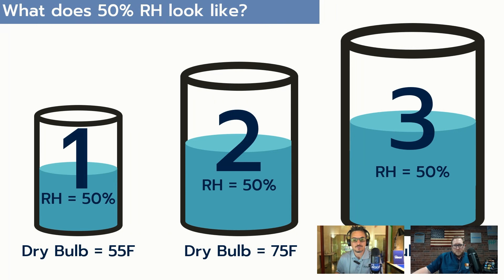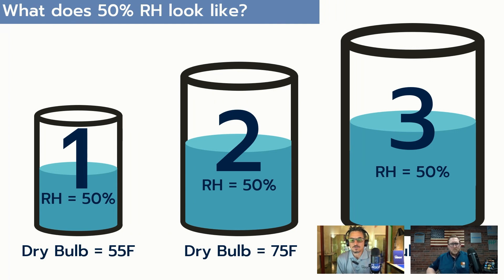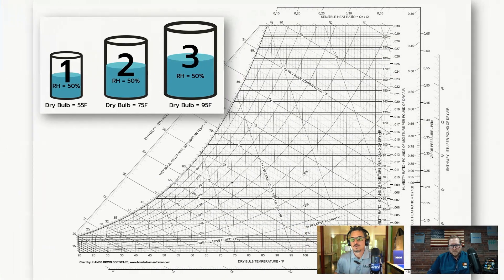We'll throw some numbers on here because we're going to reference them in a moment. What do you notice about the water volume in these three containers? It's a lot larger in container three than one. That's the flaw with using relative humidity as an indicator of how much moisture is in the air — they all have the same value, but one has a lot less moisture. It's dependent on the temperature, which is where we can get in trouble in the HVAC business.